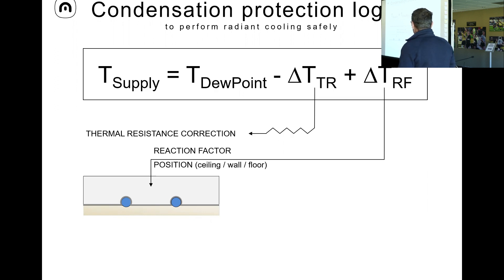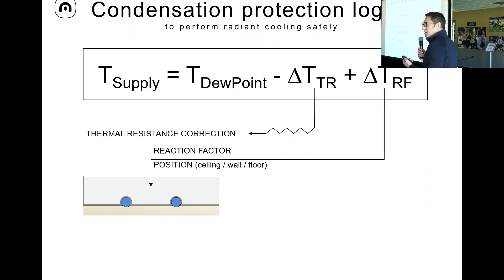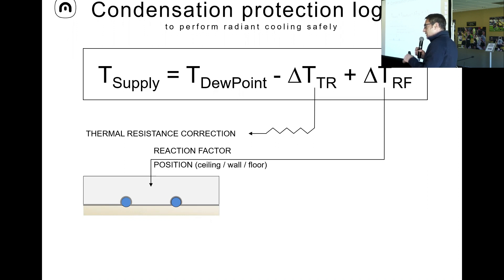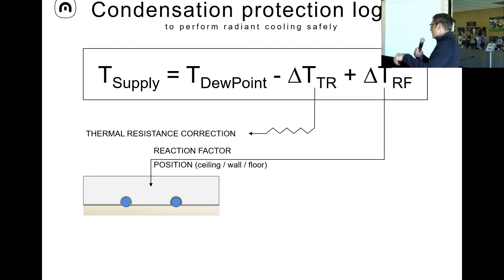The thermal correction is based on the delta T, and the safety factor is based on how fast we can change the temperature. If we get very close and something happens — say we open a window and some humidity gets in, the dew point goes up — if we are only one degree away, we could crash. We want to keep our distance based on how fast we can react. It's like racing a car: with a low-mass Ferrari, you can stay close to the car ahead; driving a truck, you keep a long safety distance so you have time to brake.